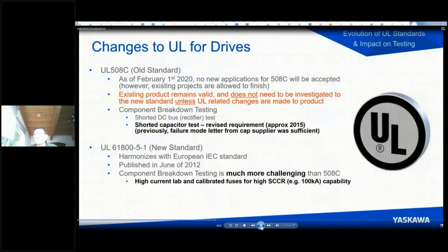And we talk about component breakdown testing. Now, this component breakdown testing is even more challenging than 508C. Okay, even more challenging than the new requirement under 508C. And the biggest change there is that for products that desire to have a high SCCR rating, and I'll use the G800 as an example, which has a maximum rating of 100,000 amps. If we had tested that under 61800-5-1, we would have to take all of our products to a laboratory that was capable of supplying 100,000 amps and to use calibrated fuses. So it's gotten much more complicated under 61800-5-1.